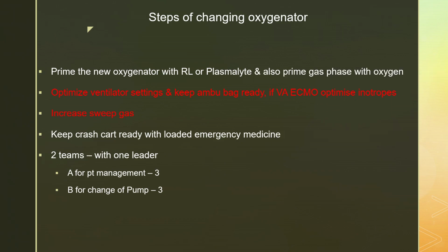Now, another thing is, what you said is right. You need to find out the countdown time. Okay. So what you can do is, see, once you are going to change the circuit or components, you clamp and you cut it. You can't do anything. If patient goes into bradycardia, you can't do anything because we already cut it. Okay. So before doing that, you do a countdown. You find out the countdown time. So when the patient is on ECMO, just put the clamp on the return line. So ECMO is stopped. Monitor the saturation and heart rate. The moment you see that heart rate which was 110 has come down to 80, 90, immediately release the clamp. And not that much time. It means your patient will give you 1 minute, 1.5 minutes, that much time to change the oxygenator.